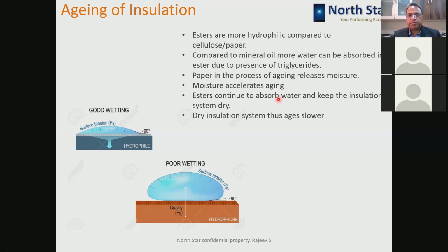Okay, so paper in the process of aging releases moisture. The external effect of moisture is also there from the breather or leakages or certain other things. The moisture comes inside the transformer. So when mineral oil is there, because it is not friendly to moisture, all the moisture goes to the comparatively hydrophilic paper. So all the moisture gets absorbed into the paper, and very little moisture remains in the oil.